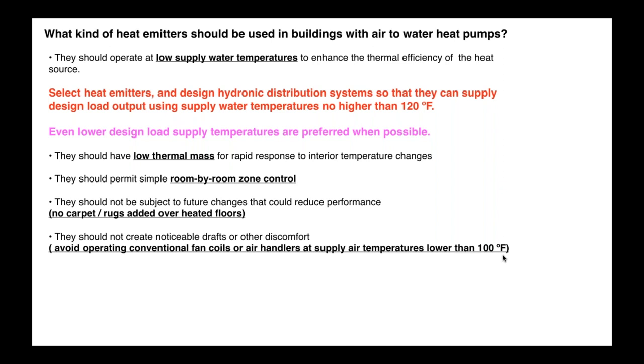If you've got a building with a lot of solar gain or potential for a lot of internal heat gain, a high mass system is going to work against you. You're going to overshoot and undershoot. Okay, now there's many examples of low temperature emitters. It could be a radiant ceiling, it could be a radiant wall. There are some radiant floor panels that are much lower thermal mass compared to a slab.